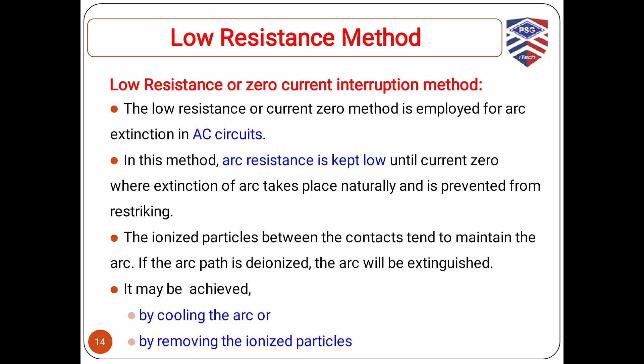So when we try to interrupt the arc at current zero time, we can prevent the formation of the restriking voltage. Already we know restriking voltage is the voltage between the circuit breaker contacts at the instant of arc extinction. That restriking voltage can be prevented when we interrupt the arc during current zero time, at the time when the current magnitude is zero. The ionized particles between the contacts tend to maintain the arc. If the arc path is de-ionized, the arc will be easily extinguished. So the low resistance can be achieved by cooling the arc or by removing the ionized particles. So these are the two methods, the high resistance method and the low resistance method, which are useful for arc interruption.